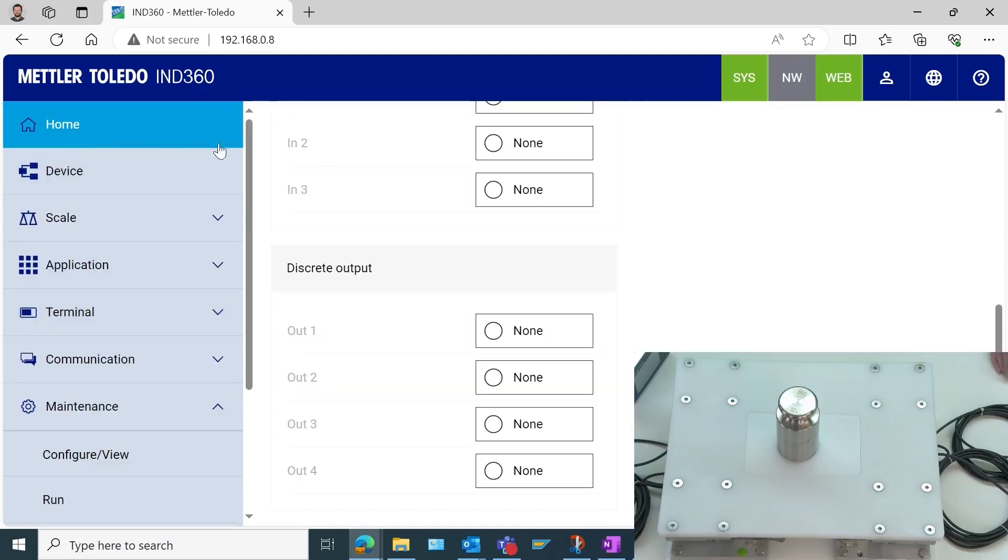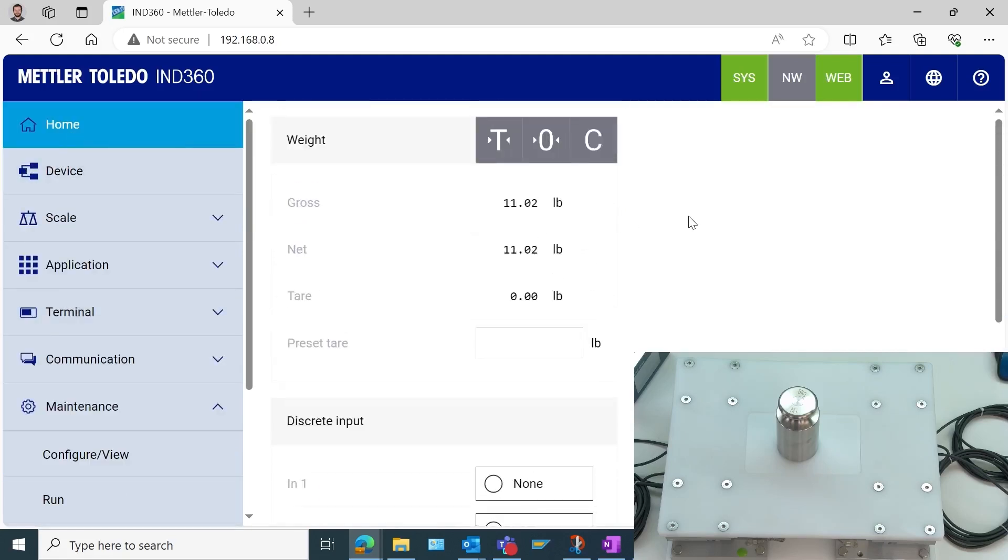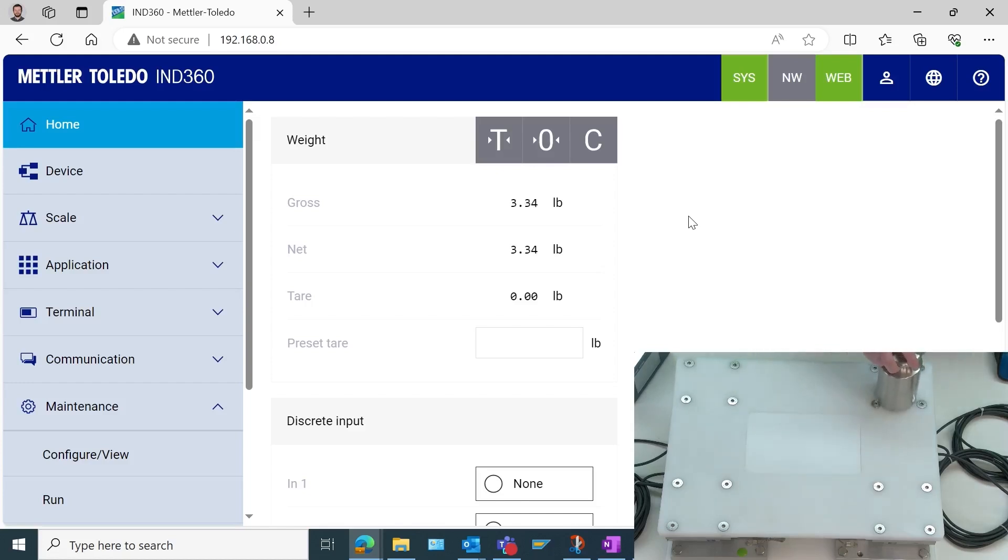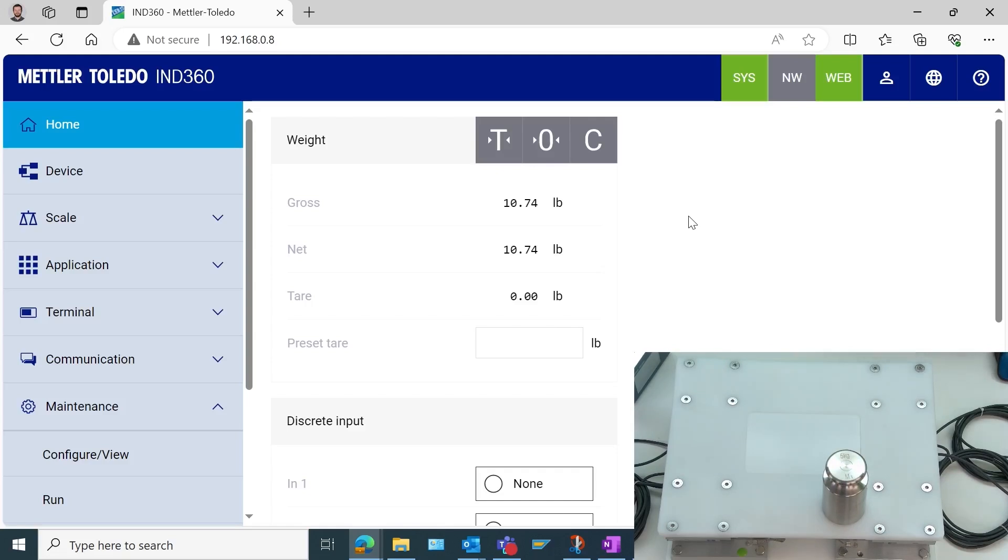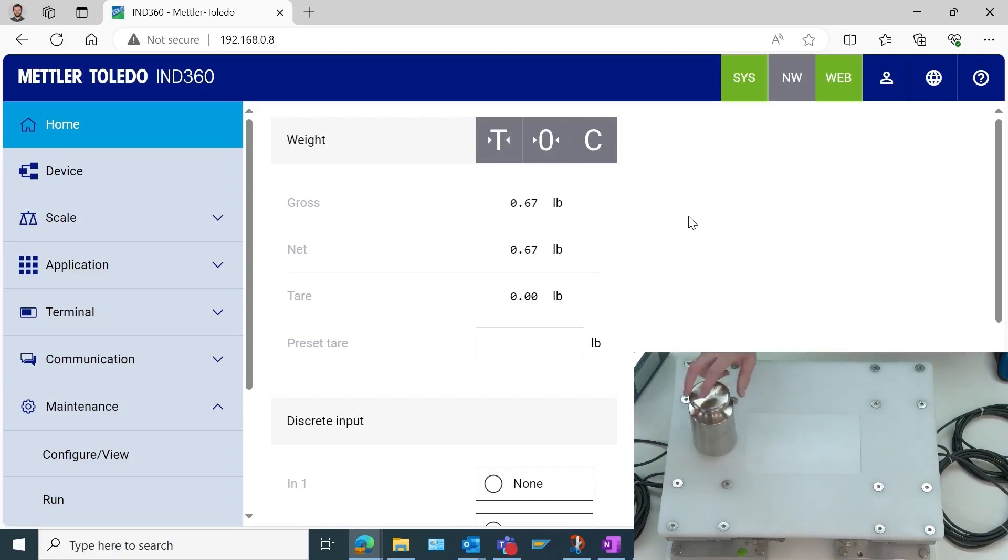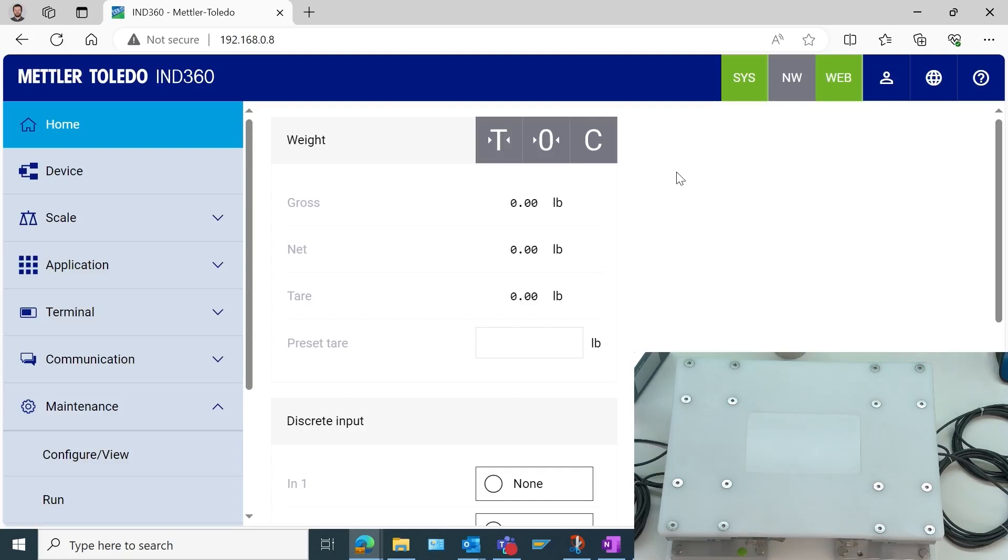Let's quickly take a look back at our home screen. We can see our weight value in pounds. And what we want to make sure is that as we move this around to different points on the scale, that we're getting the same weight value each time. So with that we can see how easy it is to set up the IND 360 MultiACM from factory defaults and get started weighing. Thank you for your time.